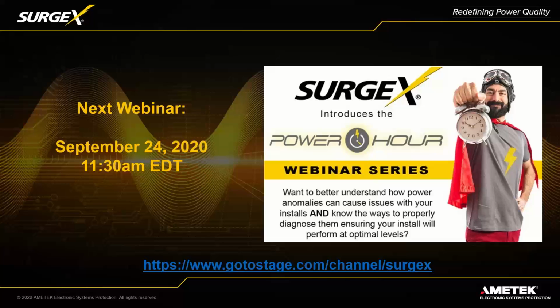When we see those Envision logs, we look a bit more in depth at how often it's fluctuating and to what level. Sometimes we see the high end go up into the high 130s and the lows go down into the 90s. When you see that persistent over time, it's usually an indication of a loose neutral issue.